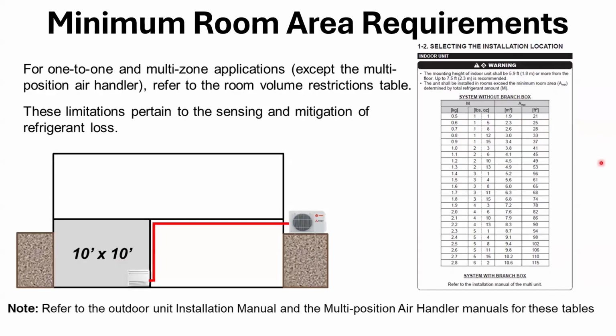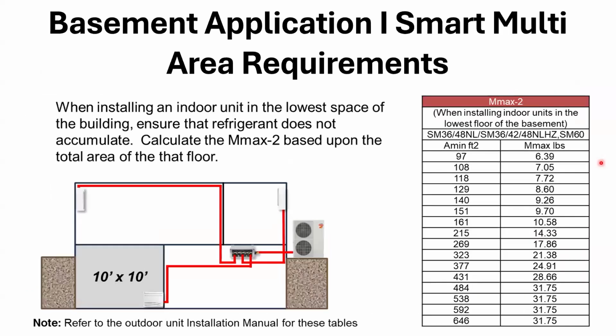So that's the 1-to-1 and multi-zone. Now, basement application, so we get to the smart multi. Area requirements: when installing an indoor unit in the lowest space of a building, ensure that the refrigerant does not accumulate. Calculate the MMAX, that's the maximum amount of refrigerant, based upon the total area of that floor. Refer to the outdoor unit install manual for these tables. So again, when installing indoor units in the lowest floor of the basement, here are the particular models, and based on your square footage, this is how much that unit can hold.